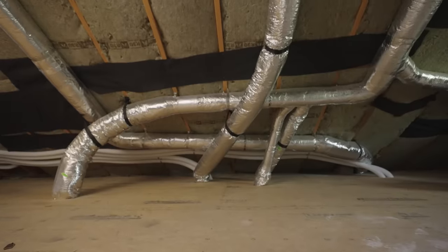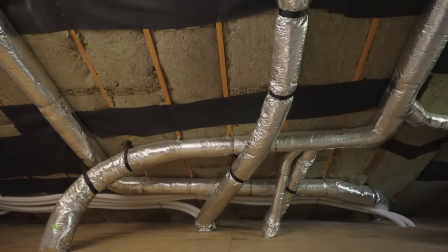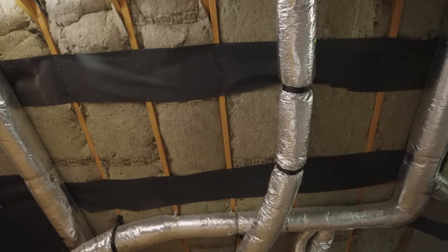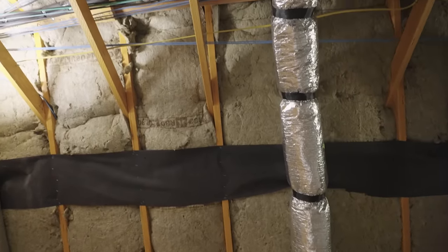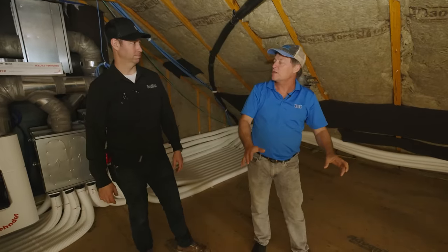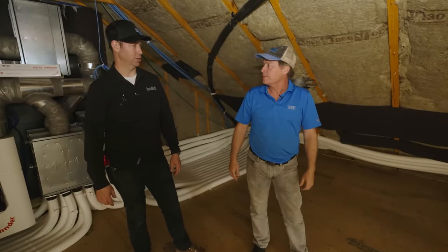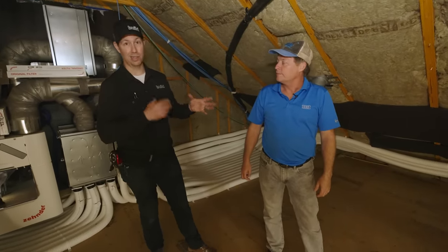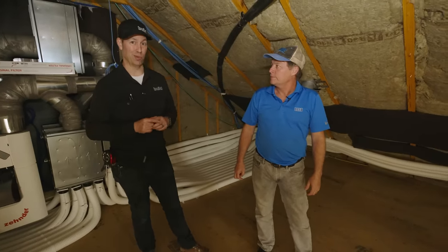None of that's going to happen in this space. And looking at the ductwork — this is stretched beautifully tight, so you're not getting any loss there. If this were a traditional attic, you would have heat flow from hot to cold going down into the house, taking dust with it. But you're not going to have any of that. Ken and I have been working on another project with a different type of insulation, but still a conditioned unvented attic. Let's head over to that project.